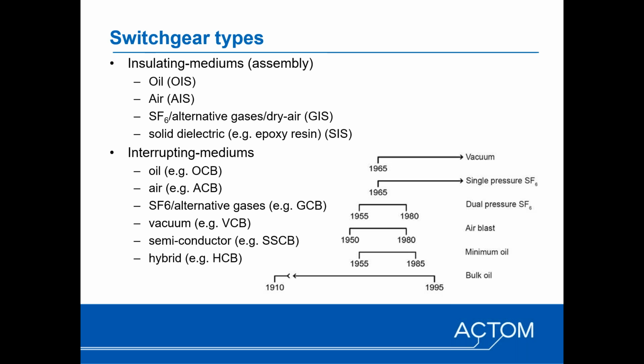And then there's dry air as well. So that's controlled air, sometimes referred to as synthetic or green air, but it's effectively just air with a controlled amount of humidity. Those collectively would be grouped as GIS or gas insulated switchgear. Probably worth mentioning that it's not always SF6 when you're talking about GIS.